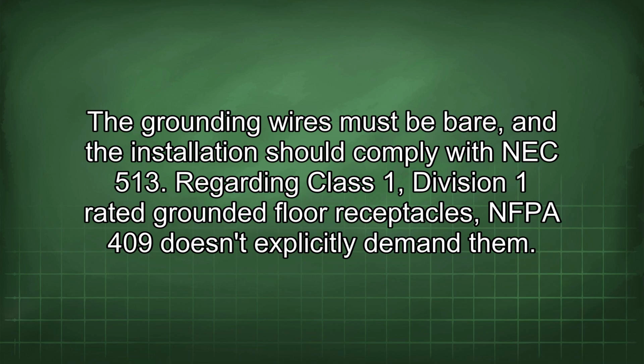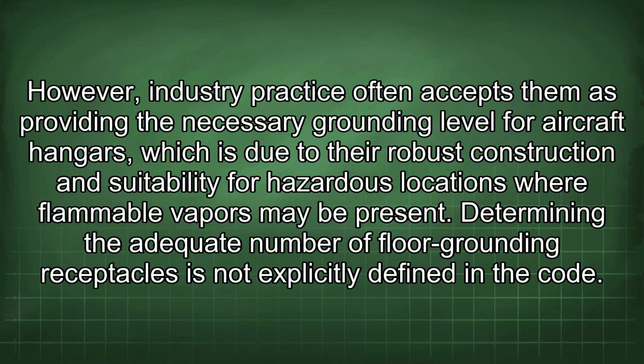Regarding Class 1, Division 1 rated grounded floor receptacles, NFPA 409 doesn't explicitly demand them. However, industry practice often accepts them as providing the necessary grounding level for aircraft hangars, which is due to their robust construction and suitability for hazardous locations where flammable vapors may be present.